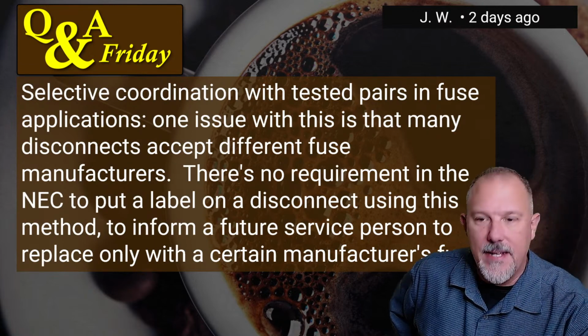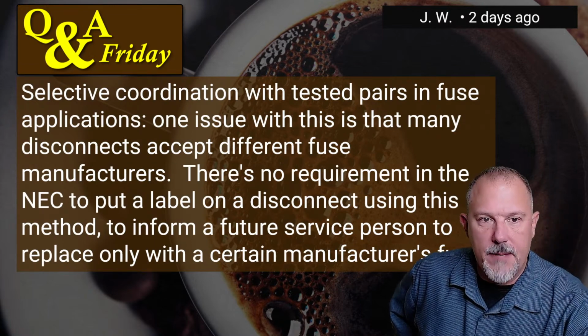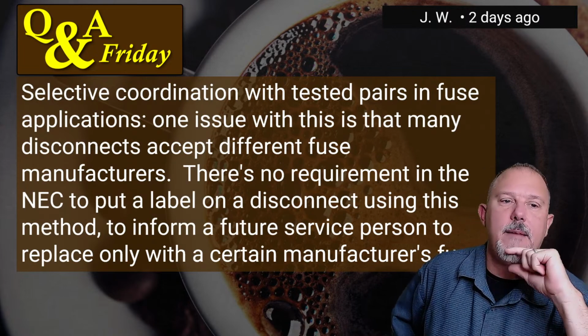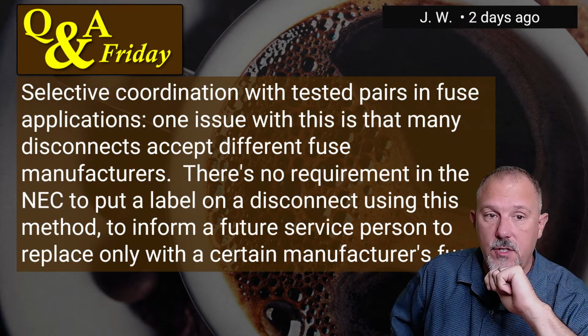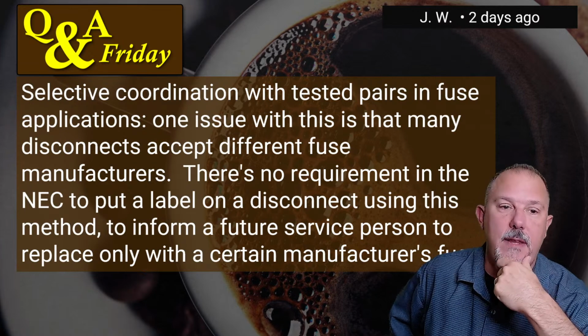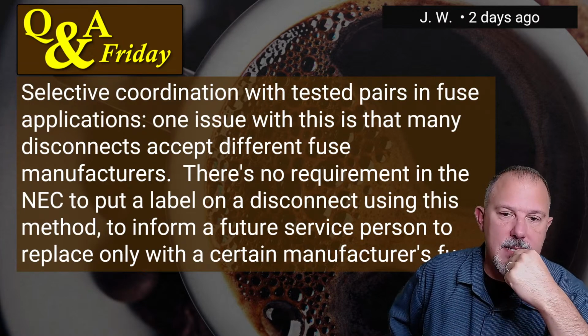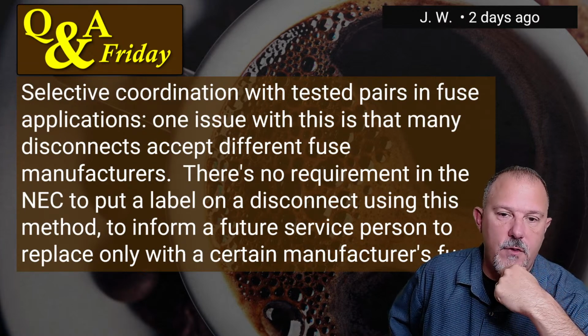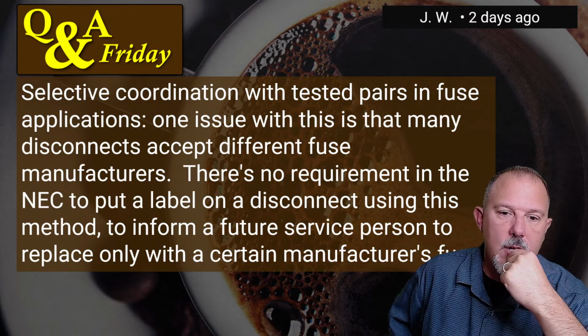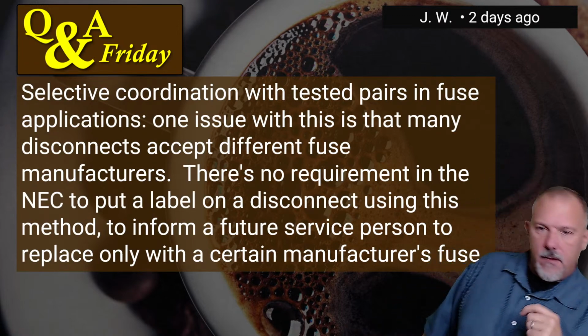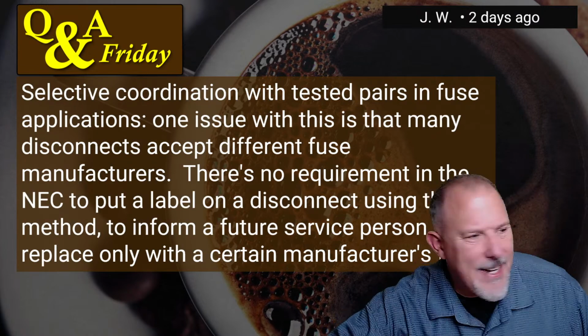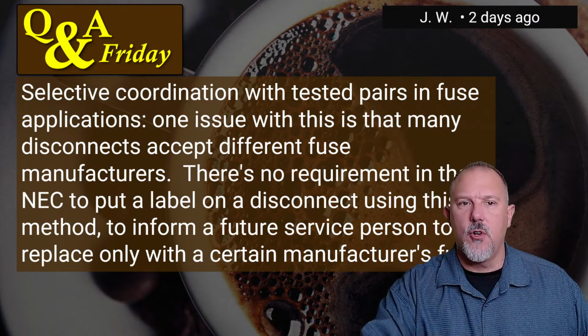Selective coordination with tested pairs in fuse applications. One issue with this is that many disconnects accept different fuse manufacturers. There's no requirement in the NEC to put a label on a disconnect using this method to inform a future service person to replace only with a certain manufacturer's fuse. I think I did talk about this. I'll just touch on it real quickly.